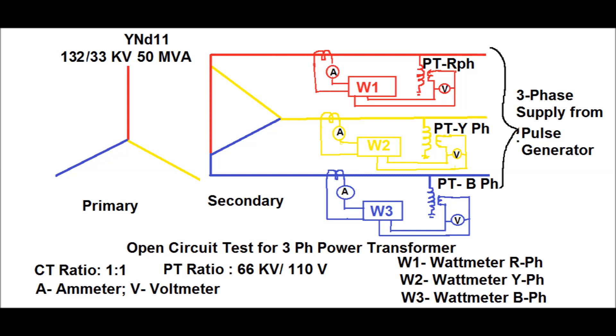The voltmeter, wattmeter, and ammeter are connected as shown in this diagram. W1 is the wattmeter for the red phase, W2 is the wattmeter connected in the Y phase, and W3 is the wattmeter connected in the B phase. A represents the ammeter and V represents the voltmeter. The ammeter is connected in all phases at the secondary of the CT, and the wattmeters are connected using the CT secondary current and PT secondary voltage.